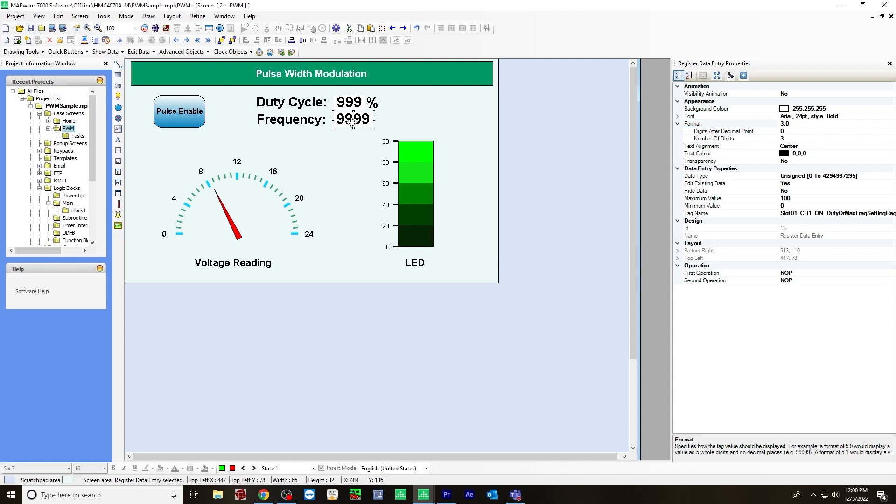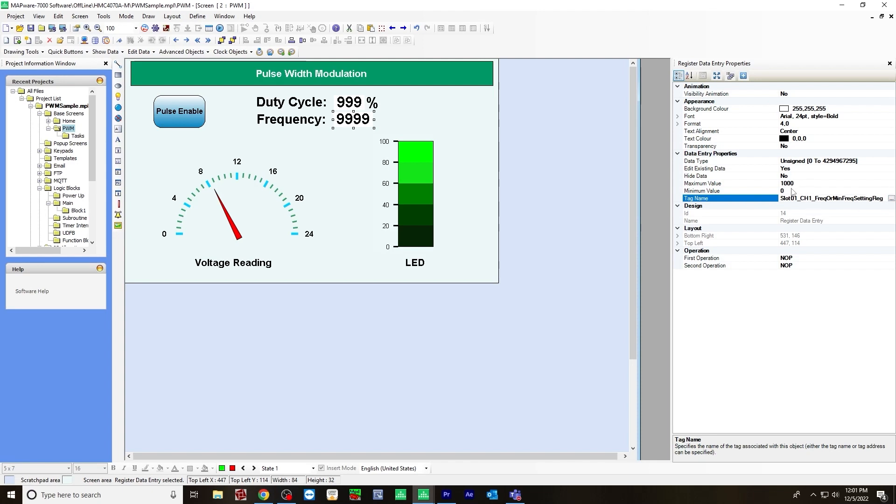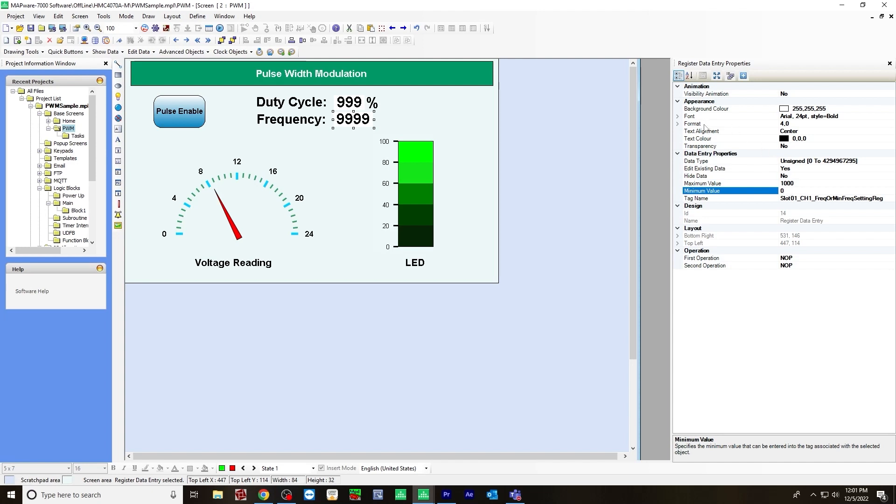And for the frequency data entry, I chose for a tag name slot one channel one frequency or minimum frequency setting register. And for maximum value will be 1000 because in this case, the maximum on the IO module I'm using is 1000, minimum zero, for format number of digits would be four.